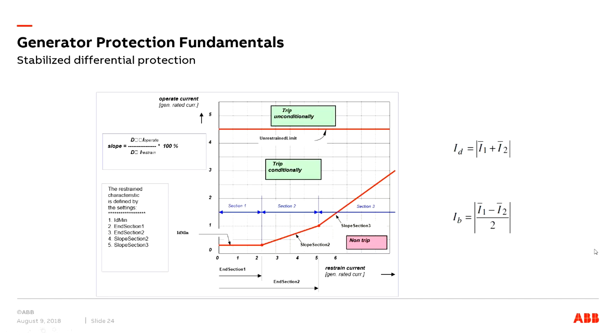So section 1 is the most sensitive part of the characteristic. In section 1, normal currents flow through the protected circuit and its current transformers, and the risk for higher false differential currents is low. So with generators, the only cause of a small false differential current can be the tolerances of the current transformers. There could be CT ratio mismatch and so on. So the slope in section 1 is always 0%. So it's a flat curve. Normally, with the protected machine at the rated load, the restrained bias current will be around 1 per unit, that is equal to the machine rated current.